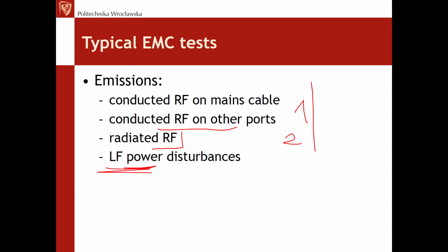We also test against immunity, but as mentioned, emissions are more important because they are regulated - first of all, no harm. Then, if our device poses no problem to the environment, we can test it. Plenty of tests are defined for testing the immunity of our devices against conducted RF, radiated RF, voltage dips, magnetic peaks, electrostatic discharge, and fast transient voltage surges.